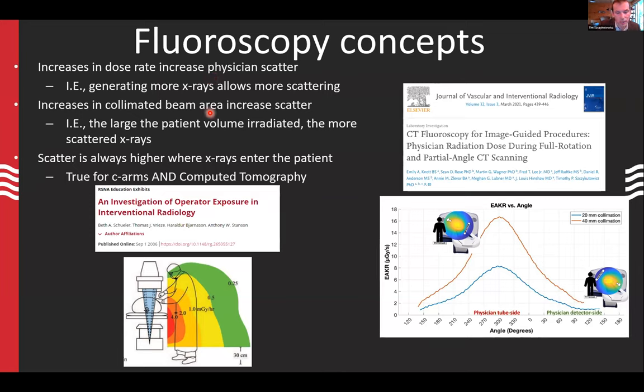Increases in collimated beam area matter too. If your physicians are using a 4 centimeter or really big beam collimation to progress a needle through, they really shouldn't be doing that. We should have gantry tilt on, trying to get in the plane of the needle. Our physicians will only use that big beam collimation if they're kind of lost inside the patient. But for most needle guidance work, it's a very narrow beam, around 7.5 millimeters.